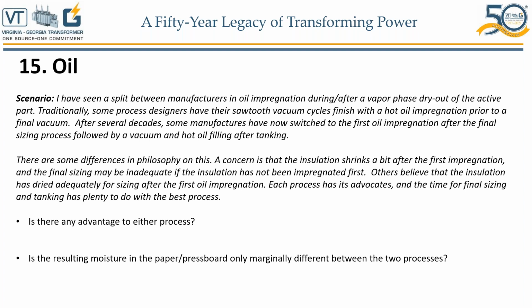not the final vacuum after tanking. After several decades, some manufacturers have now switched to the first oil impregnation after the final sizing process, followed by a vacuum and hot oil filling after tanking. Yes, there are different methods, and there are actually still suppliers, and depends on the size of the transformers. There's some plants maybe still not even using VPD, just using conventional dry oven. There are some differences in philosophy here.